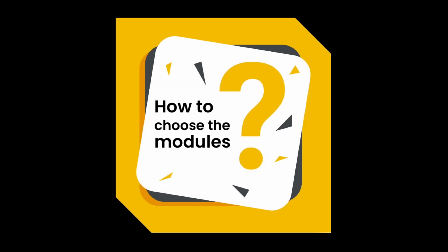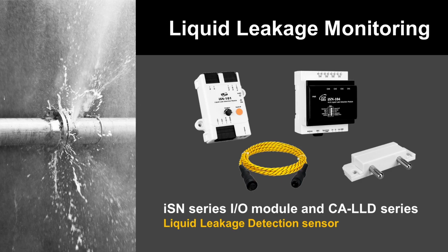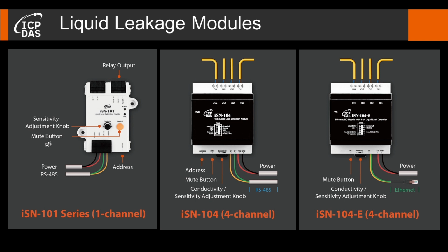In the above three case studies, we can see that liquid leakage and air quality monitoring can be applied in many different fields. However, we have mentioned many different modules. The problem is how to choose a suitable module for your environmental monitoring solution. First is liquid leakage monitoring. ICP-DAS liquid leakage modules are a combination of the ISN series IO module and CALLD series liquid leakage detection sensor. ICP-DAS provides three types of liquid leakage modules: ISN101 series, ISN104, and ISN104-E. The detective distance of the three types of modules can all be up to 500 meters.